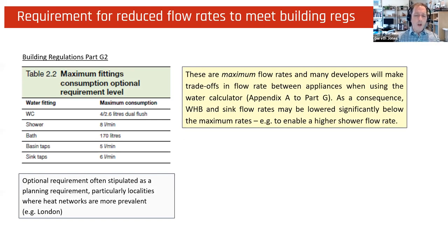Conscious of time. So we're balancing off that 45 degrees within 45 seconds. We've got a requirement at the same point in time for reduced flow rates to be used in building regulations. In particular, if you look at Part G, there are optional requirements under Part G. We tend to see those being used in localities where heat networks are more prevalent. And if you just apply this, there's a standard table that you can apply to use those. You see that kitchen sink taps, for example, tend to be around 6 liters per minute as a maximum. You can obviously do your own calculations to go above that if you make flex to other areas. But what we're seeing is that actually quite often in practice, trade-offs in flow rates are being used, where people are going below the 6 liters per minute because they're trying to get a higher shower, for example.